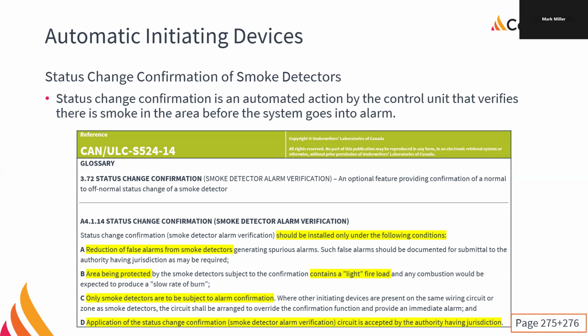all the smokes in the patient rooms had status change confirmation, which kind of makes sense because when they upgraded the fire alarm system the previous time, which was like 1993 or something like that, smoking was still allowed in certain parts of hospitals. It was a whole other world back then. And the number of patients that would just light up a cigarette in a room was insane. It's not that common now, right? On a larger hospital, it's probably only once or twice a month. But it used to be like near constant. And so they put in status change confirmation to delay those alarms.